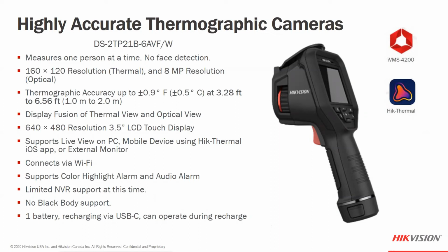If I'm walking behind something or making a measurement and the background has hot light fixtures, or a thermostat on the wall that could be hotter than my skin, or I'm carrying a cup of coffee or tea, this could affect the measurement range. So because there is no face detection, this is going to be a much more precise measurement, one person at a time.